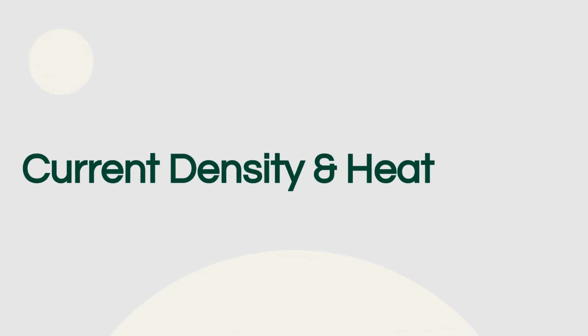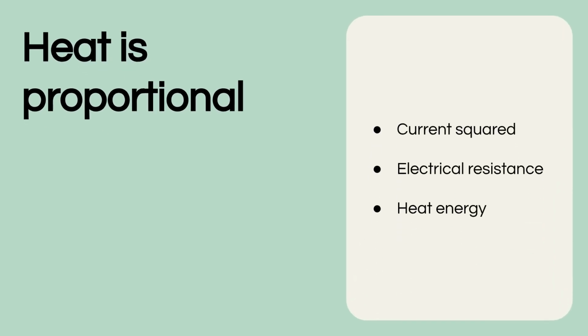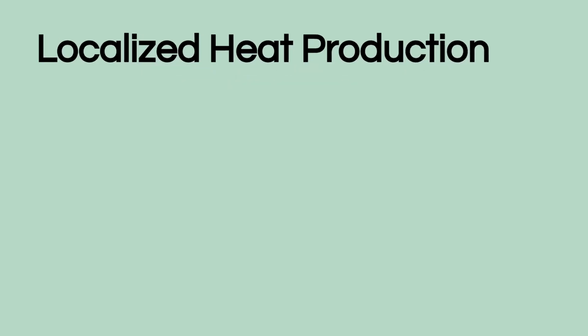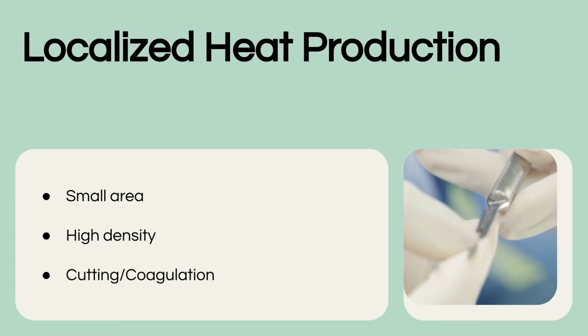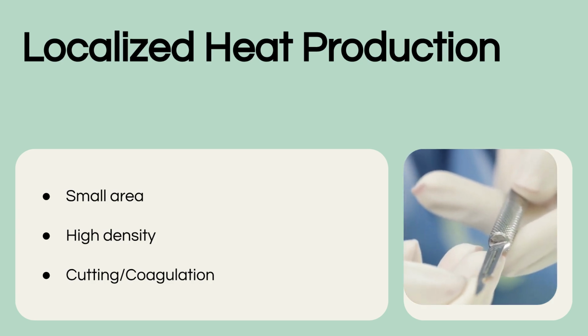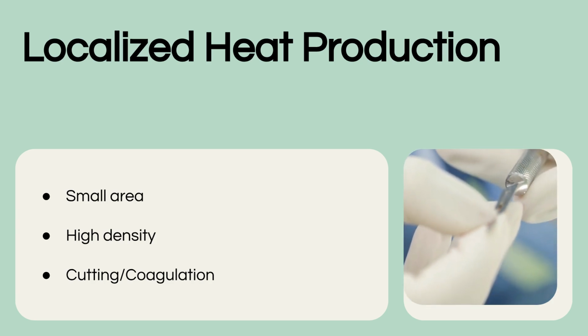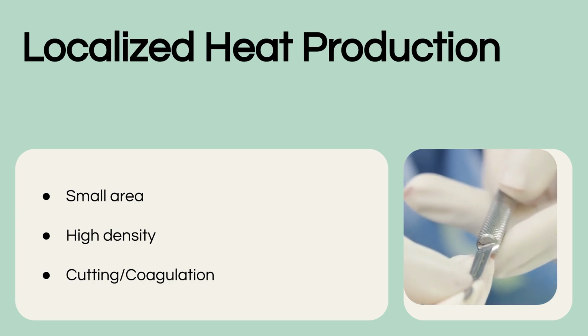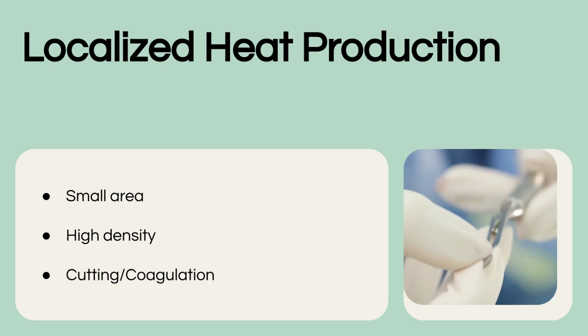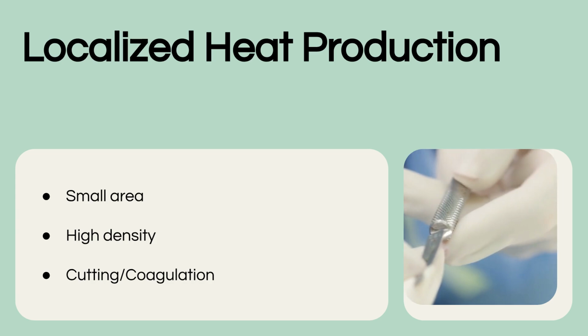The effectiveness of diathermy relies heavily on the concept of current density and how heat is produced. In physics, the heat energy produced is directly proportional to the square of the current multiplied by the electrical resistance of the tissue. Heat production is heavily dependent on current density. At the small surgical tip, high current density generates intense heat, enabling cutting. Conversely, a large area, like the patient plate, ensures low current density and minimal heat to prevent burns.